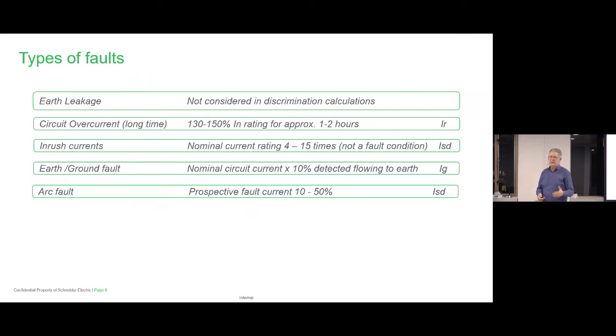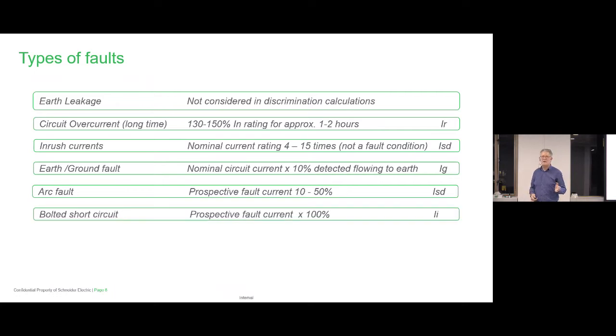Arc fault, that's one of the worst ones. That's the short circuit. You're going to see 10 to 50% of the prospective fault. The prospective fault is your job, or the engineer's job, when you do the design with the software that you use. You're the one determining what that is. And the bolted short circuit is the worst one you can get. You can see 100% of the prospective fault level sometimes, but that's what you design the board on. You start from there. That's what we would expect you to do, even though that's probably not the case.